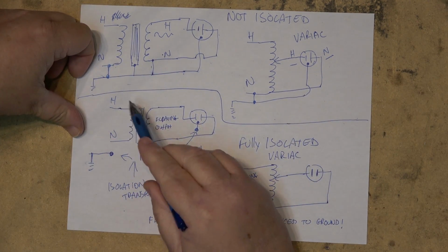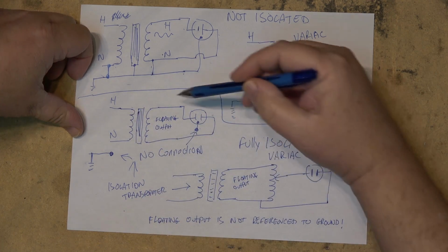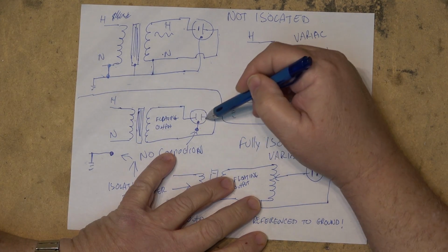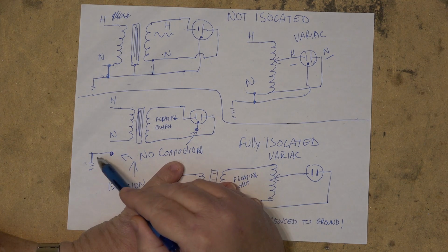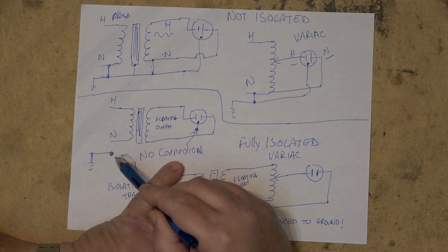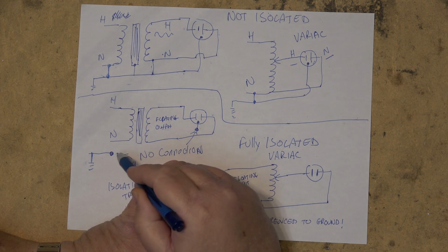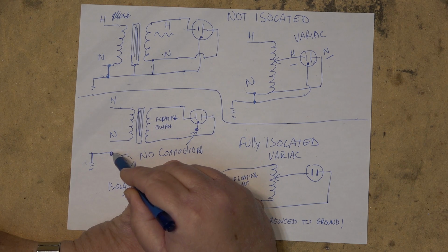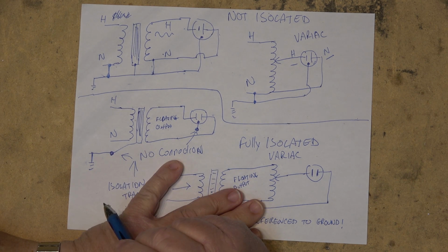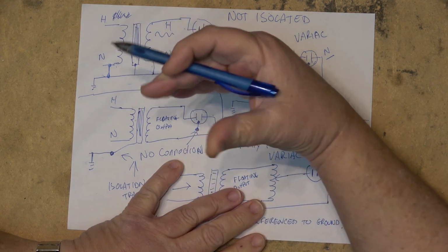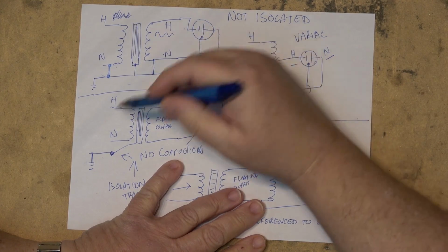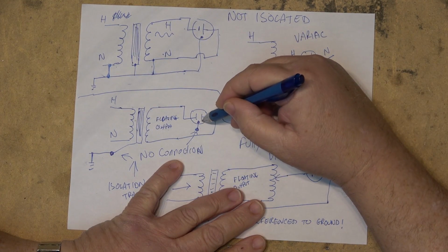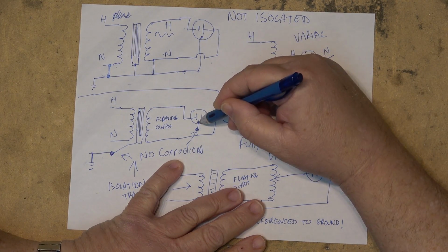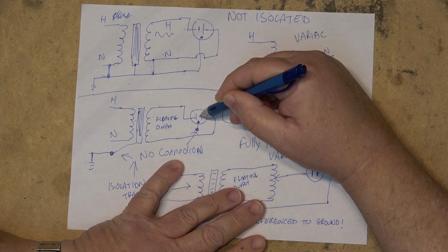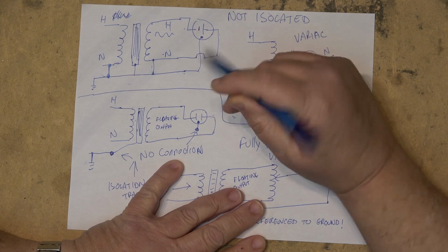A true isolation transformer is this one here. You have a hot and a neutral going into your primary. Your secondary is connected directly to the outlet. There is no connection. The ground wire, if there's a ground plug on here at all, would be not connected to anything, or at the very, very worst case scenario, it might be grounded to the case, just so that the transformer itself, the actual case, is grounded. But that is it. There will be no connection to a third plug. In fact, most of them will not even have a 3-prong plug. They only have a 2-prong plug on the output to prevent someone from plugging a 3-prong outlet into it.